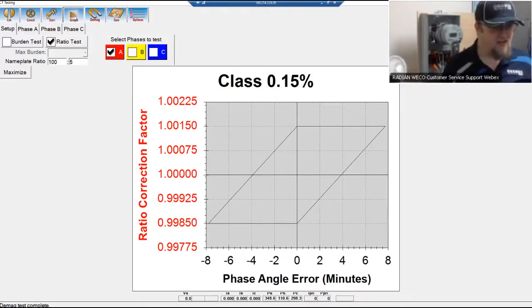When would you run demag? You would typically run that if your ratios are running a bit high, or if you think something has happened to the CT's core to have it become magnetized. Typically, you'd be reading a little higher. So these 105 CTs were magnetized. I might be reading 110, 115, something a little higher than what I would normally expect from that. So you can try to run the demag, and the RW will attempt to demagnetize that CT.